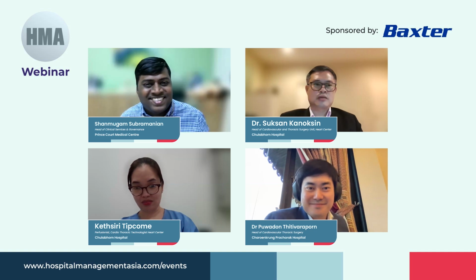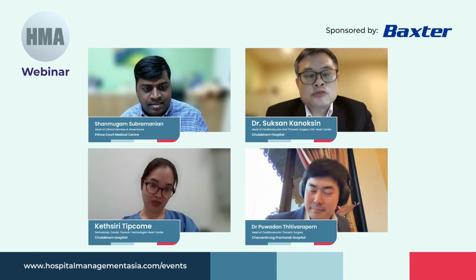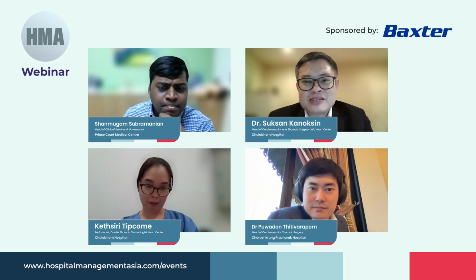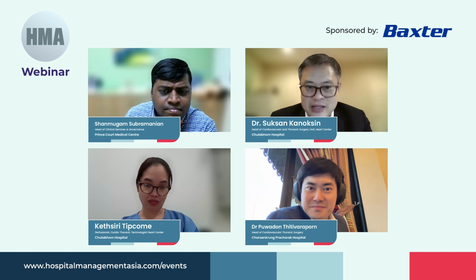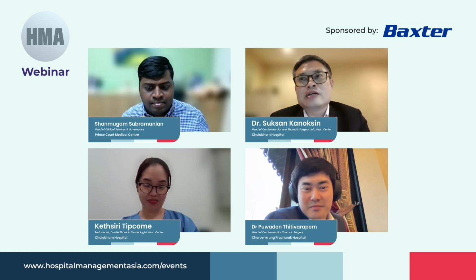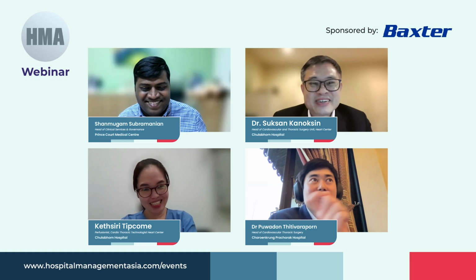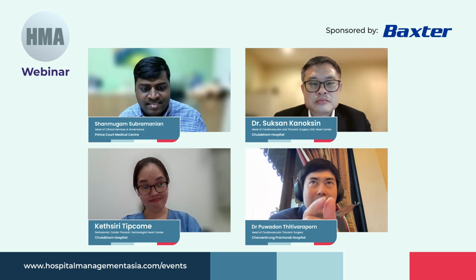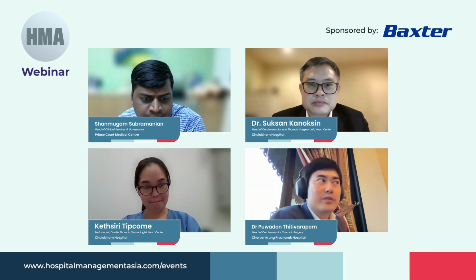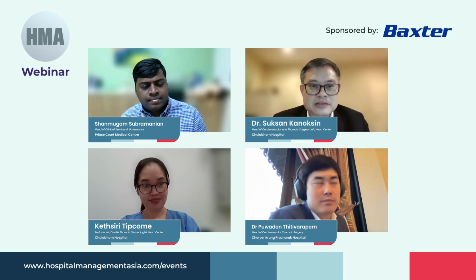What do you think, Dr. Suksan? Yes, I agree with you. And maybe another issue we should be concerned about is the invisible dangers of the hybrid OR. We should be aware of the radiation. The radiation in the hybrid OR is very dangerous, because if we don't have good protection, someday... As I know, if we renovate the old room, we need at least a very thin but very high quality lead for protection. But if we build a new one, we could build a thick wall, or we could put some thin lead inside at the same time. Yes, we have an option.